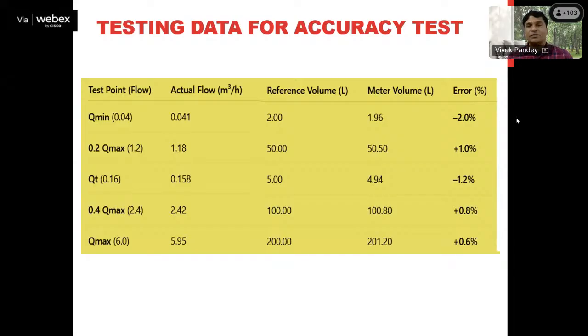Suppose 5 points we have selected. At all these 5 points, we will perform the transaction through the reference gas meter as well as the gas meter under test. We will calculate the error and compare these errors with the prescribed tolerance. Whenever you compare these errors with the prescribed tolerance, make sure that up to the transitional flow rate the MPE is different, and above the transitional flow rate it is different. So accordingly, we will compare it.